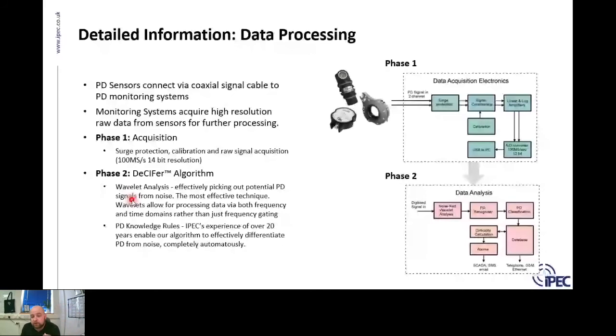The next stage is the knowledge rules. So built into our system is this experience of 22 years of PD monitoring of cables that we've done, and then we can apply those PD knowledge rules and decide if something - the system can then decide if something is in fact cable PD, is it local PD, is it switchgear PD, and classifies it appropriately.